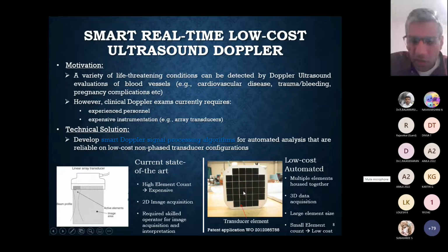As compared to that, what we have developed in this project is a very simple ultrasound transducer configuration. As you can see here, there's a very limited, small number of elements. This particular transducer has only 32 elements, compared to 256 elements, or sometimes 512 elements that may be needed on the transducer on the left.